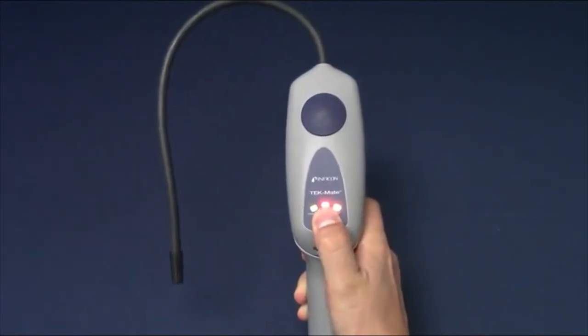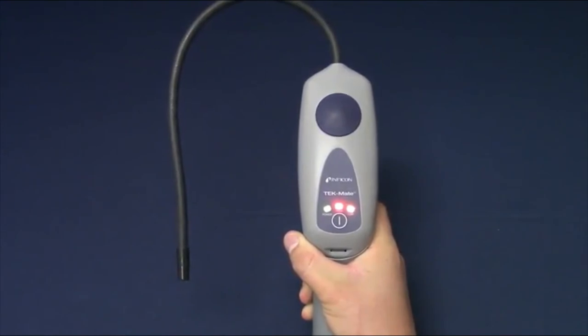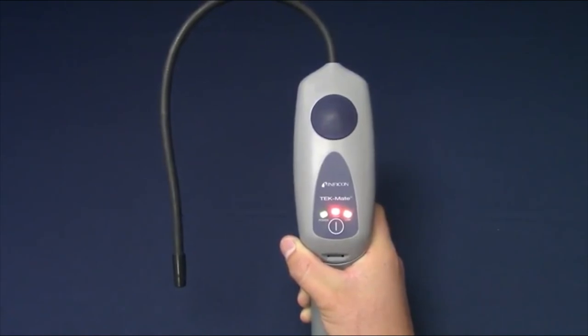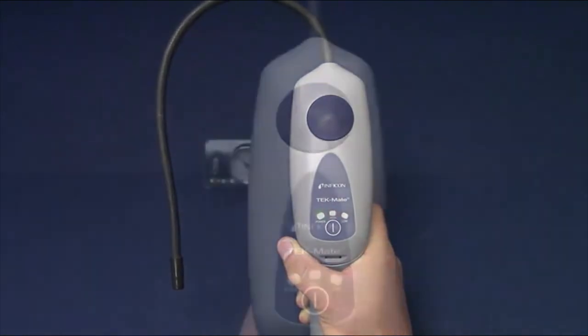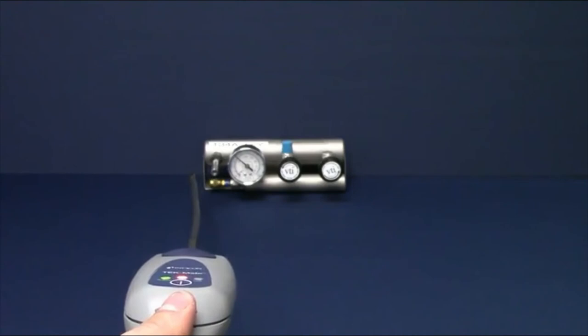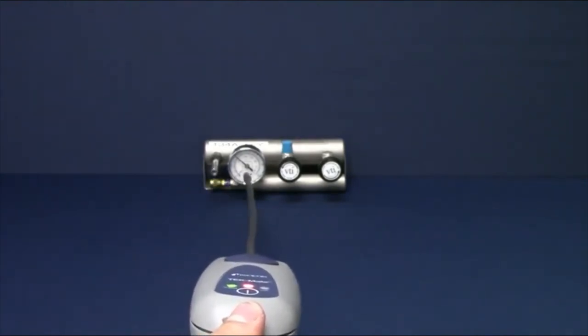Once batteries and sensor are installed, long-press the power button to turn TEK-Mate on. On startup it will alarm to indicate the sensor is warming up — this could last a few minutes. Eventually it will slow to a steady beep, indicating TEK-Mate is ready. TEK-Mate always starts in high sensitivity, useful for finding the general source of the leak. Move the probe slowly around the suspected leak area; TEK-Mate will beep faster the closer it is to the leak.